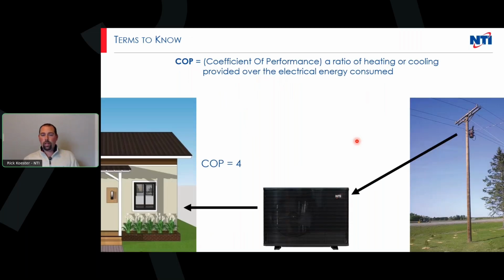When we talk about COP, that COP is our efficiency. If you're familiar with our boilers, we talk about AFUE, that's how efficient that boiler is going to be at a given temperature. AFUE is really affected by the water temps that we bring back. The lower we can bring it back, the higher the efficiency. Contractors are so used to pumping 180 degrees through their systems, and they're bringing back hot water at 160, 170 degrees. We're really not running that system properly enough to get that 96% that we say we can get out of that boiler. Typically, running efficiency is probably going to be somewhere around 84, 85%. So it's very low.